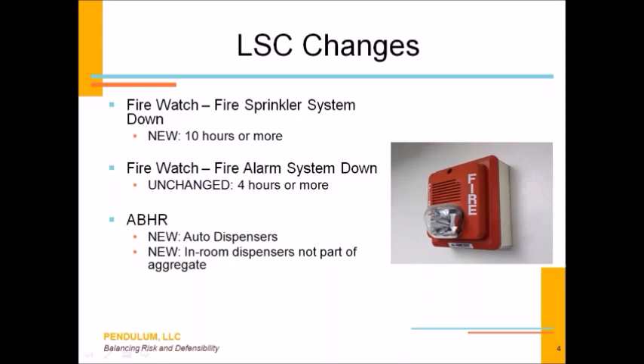a 24-hour period. So let's say you had a failure of a fire alarm system, or a sprinkler break, or you're having service done on any of those systems. If those systems were down for four or more hours in a continuous 24-hour period, you were required to enact your fire watch policy. There's been a big change when it comes to the sprinkler system. No longer is it a four-hour threshold. It has now been changed to a 10-hour threshold. So if your fire suppression system is down for 10 hours or more in a 24-hour period, that is your trigger to initiate a fire watch.